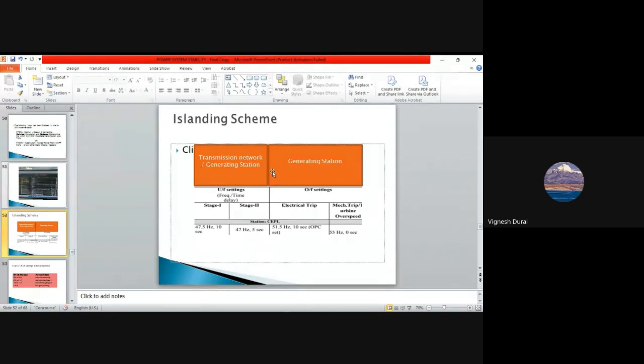In the islanding scheme, if our frequency reaches 47.5 and prevails for 10 seconds, it will have a stage 1 tripping, where it will trip both generation and load. For the transmission network and generation, both will be tripped. If your frequency is below 47.5 for 10 seconds, or 47 hertz for 5 seconds, it will automatically go for stage 1 tripping and stage 2 tripping. We have many feeders for this, because it will completely island a network.